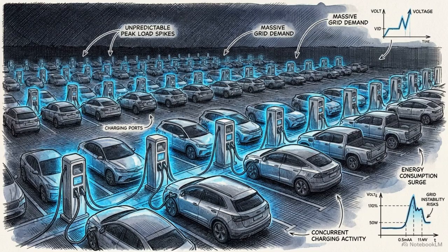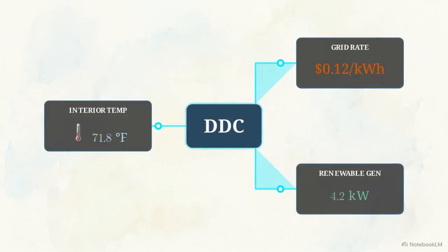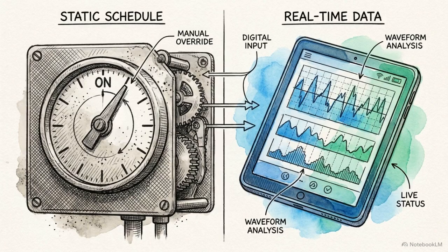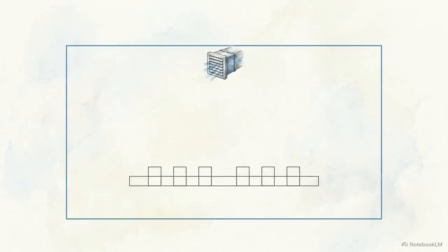The engineering solution relies on direct digital control, integrated into complete building automation systems. Instead of running blindly on a static schedule, a building automation system uses real-time data to optimize internal mechanical loads, like adjusting variable air volume systems to match exact room occupancy at any given minute.